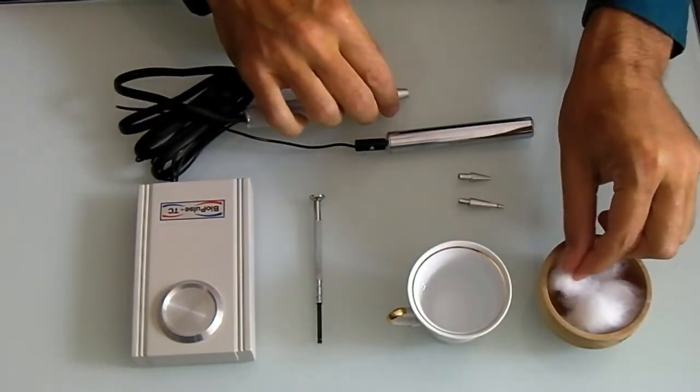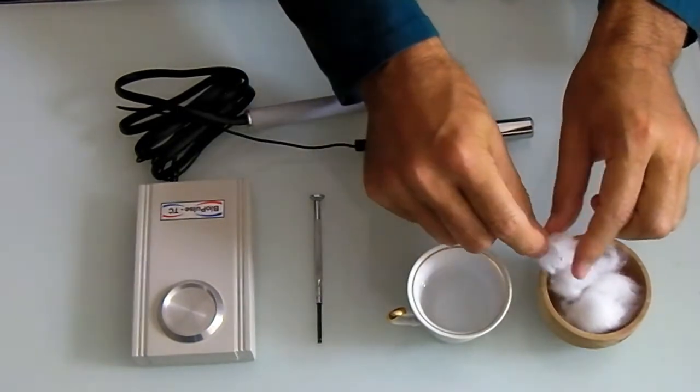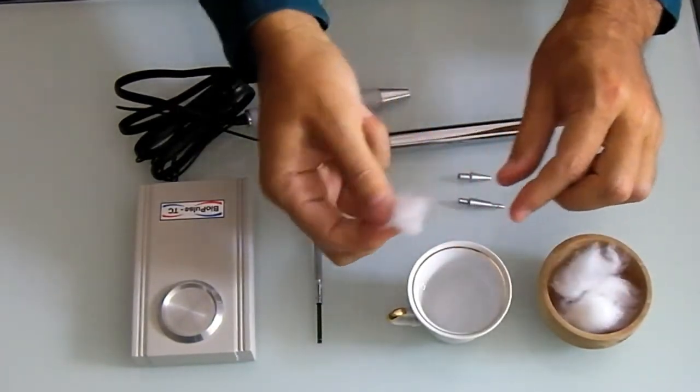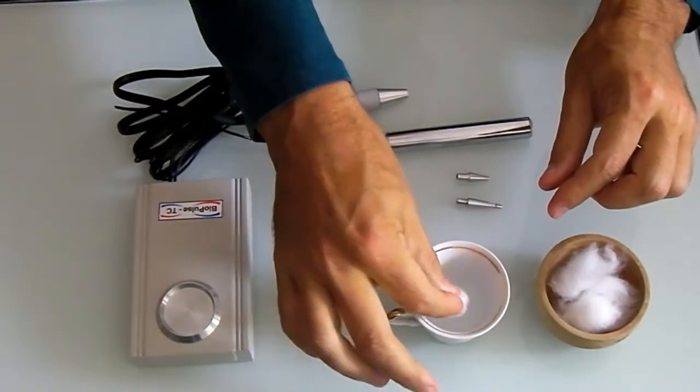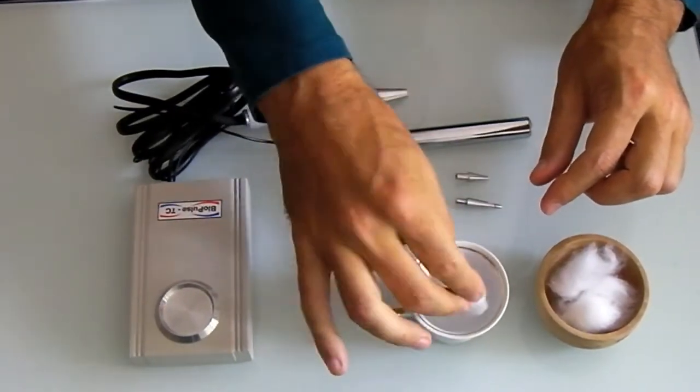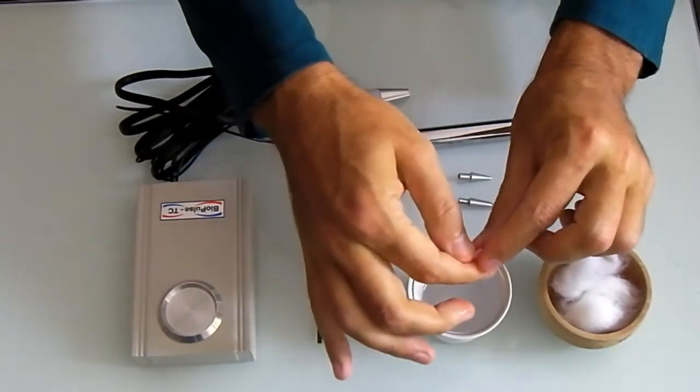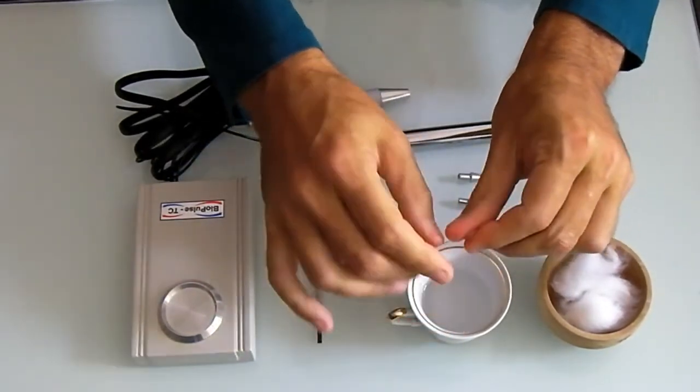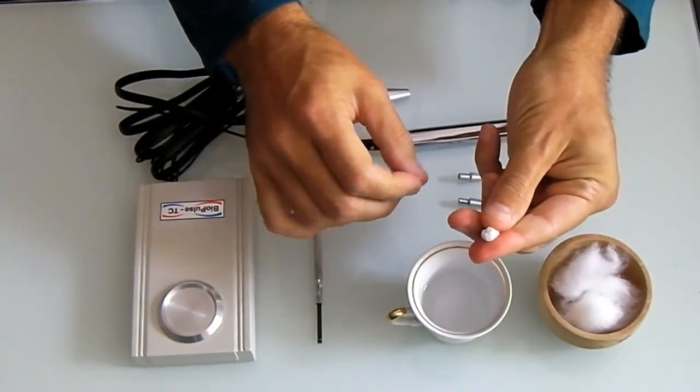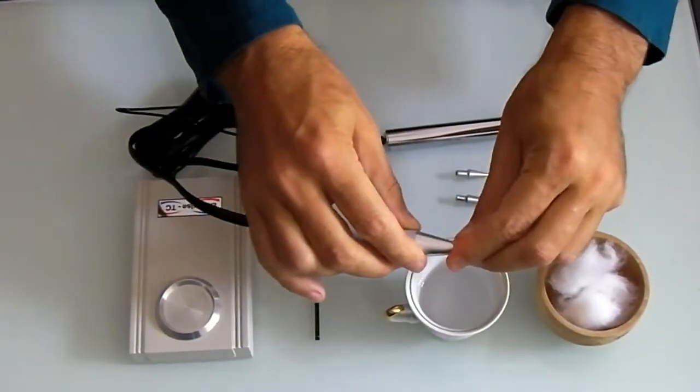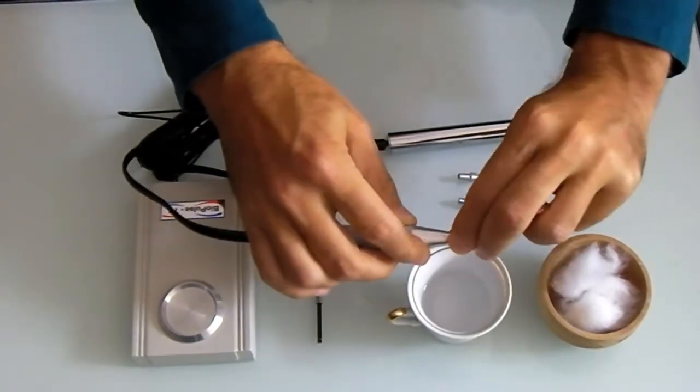The next step is inserting the cotton swab in the hole of the detecting probe for making Ryodoraku measurements. You moisten it with water or any other spirit, for example alcohol gel, and put the cotton swab into the detecting probe.